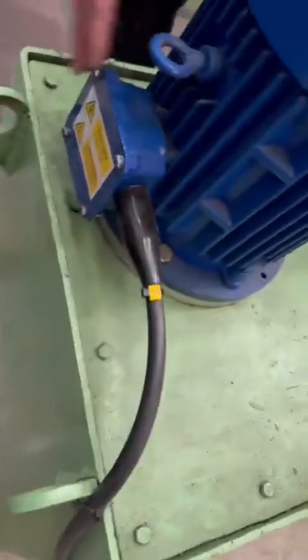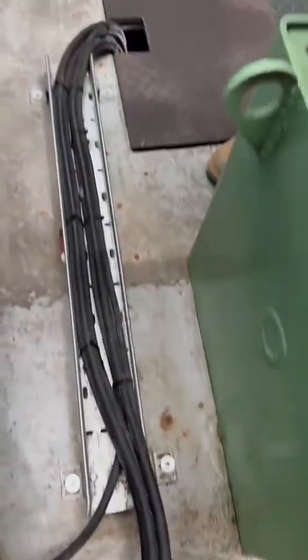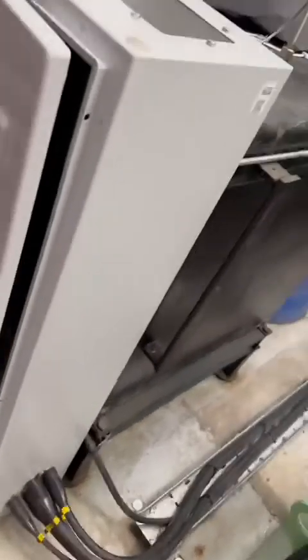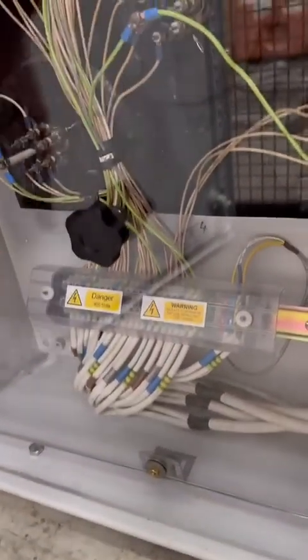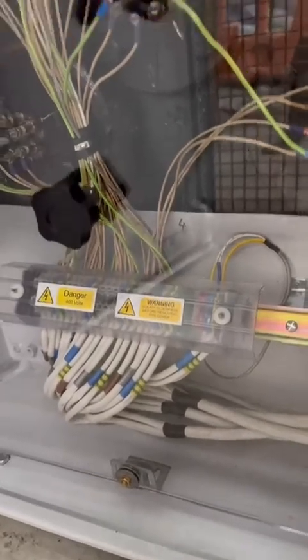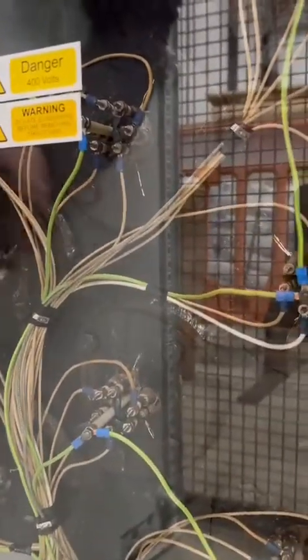The motor has been rewired, armoured cable, proper earthing, labelling. I don't know if you remember these heaters. I had the old baked bean tins on. Well, now we've got the armoured cables connected in. We've got terminations in the bottom, heat-proof sleeving, proper identification. We've now got earth bonds throughout. We've taken away the bean cans, so we can actually see what's going on here.